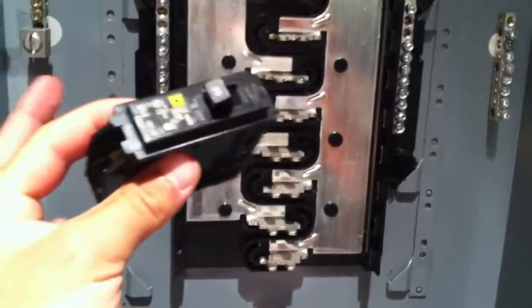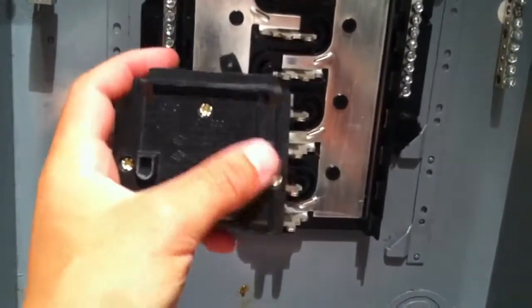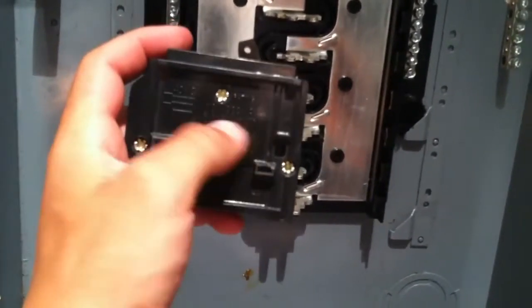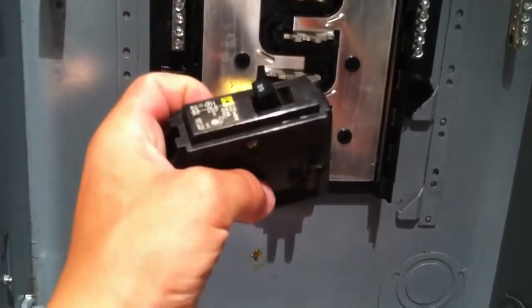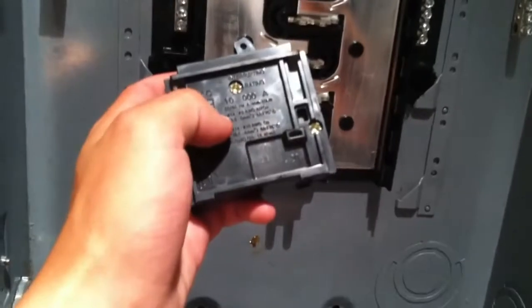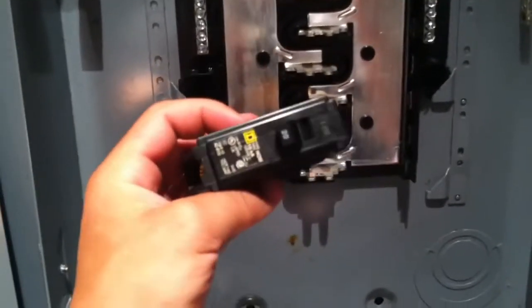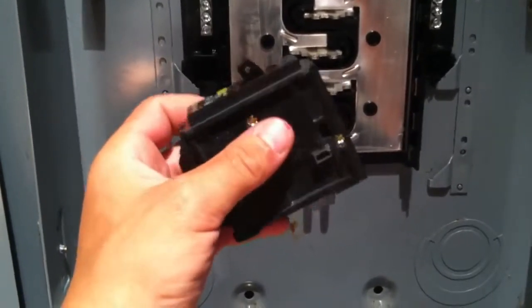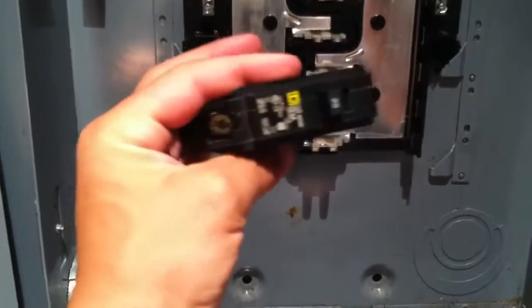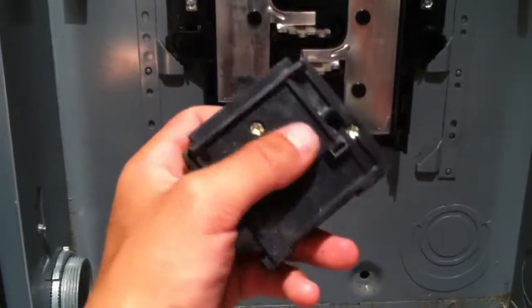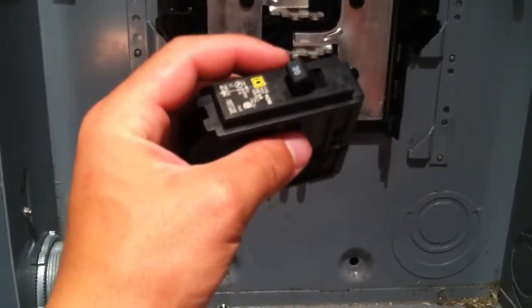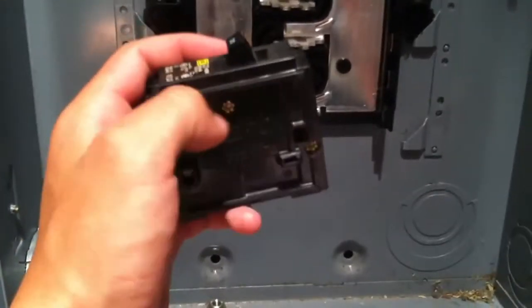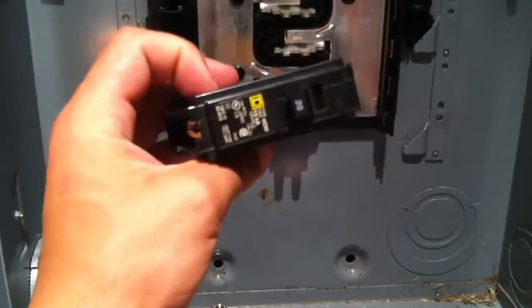It basically is simple. It pulls from the hotline and goes out, and it monitors the current. So let me explain how this works real quick. When you have electric current flowing through here, if you guys don't know, electric current when it flows through something makes a magnetic field. So it actually has a wire in here where all the current passes through, and it runs through a little iron bar, and it overcomes the tension of a spring in here. There's a spring in here, and if it's able to pull past a certain point, there's so much current through there that it's around 20 amps plus or minus a certain percentage. I don't know. It has to be pretty close to be UL listed. That'll mean that it's pulling over 20 amps, in which case it'll overcome the tension of the spring and it trips the breaker and breaks the circuit. Okay, so that's how a normal AC circuit breaker works.